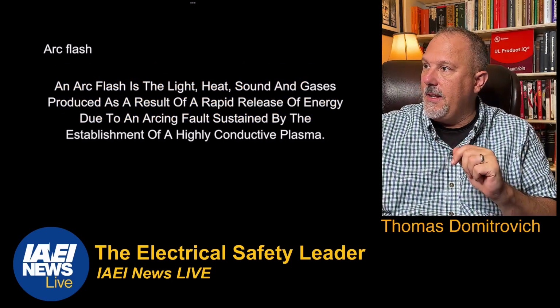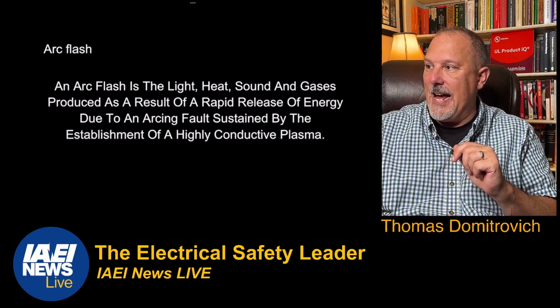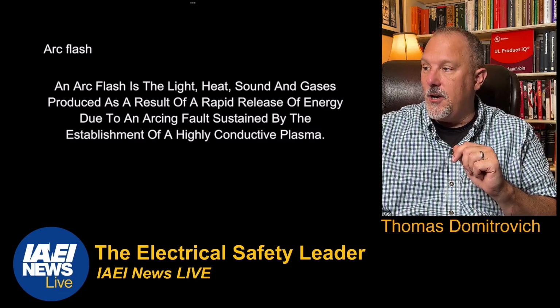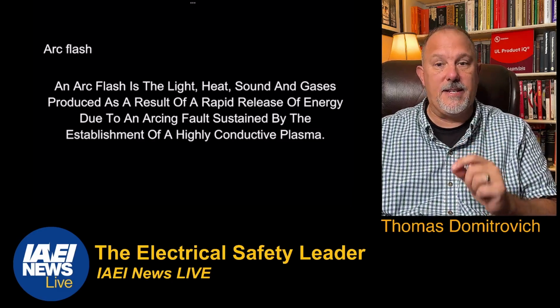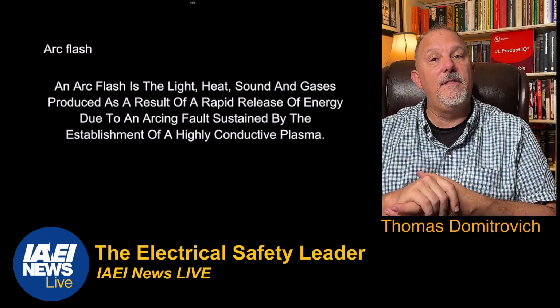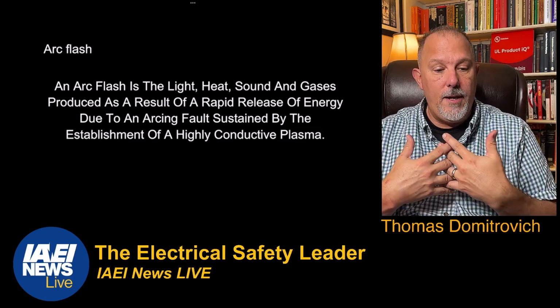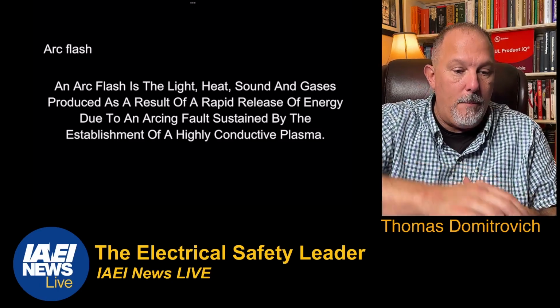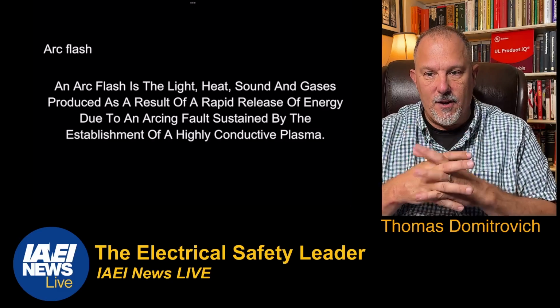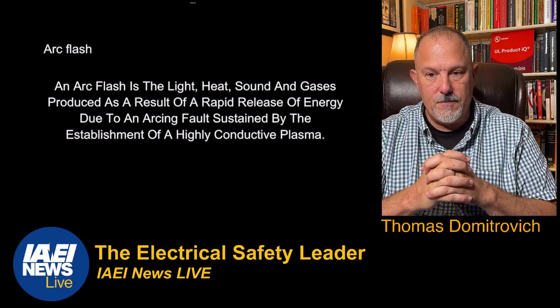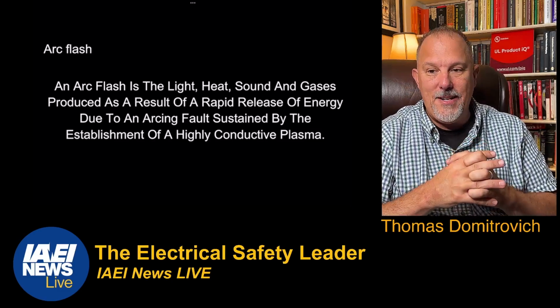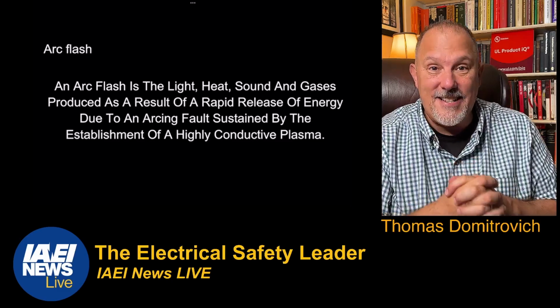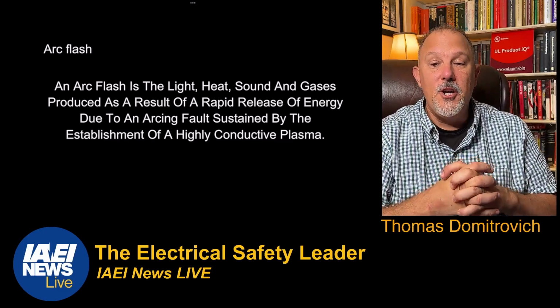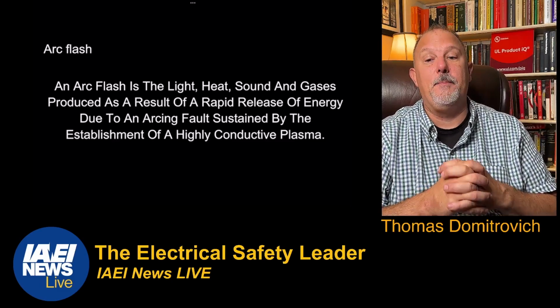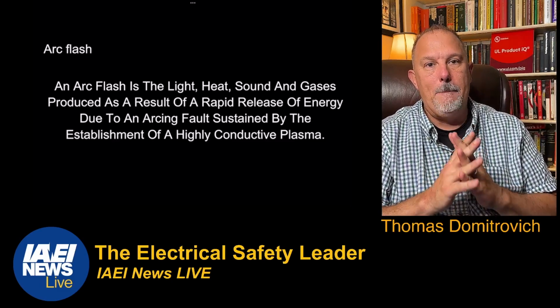Now, an arc flash. Okay, let's take a look at definitions. Arc flash is still not a defined term in 70E. Now, when you have a lack of a definition, you know what that means? We have the opportunity to make one up. So I came up with this. An arc flash is the light, heat, sound, and gases produced as a result of a rapid release of energy, an unintended rapid disassembly in the field, due to an arcing fault sustained by the establishment of a highly conductive plasma.